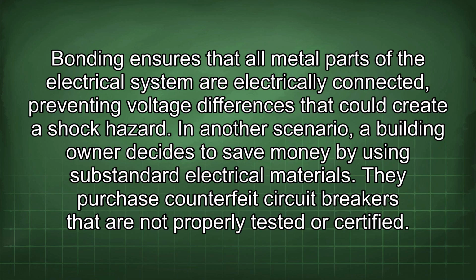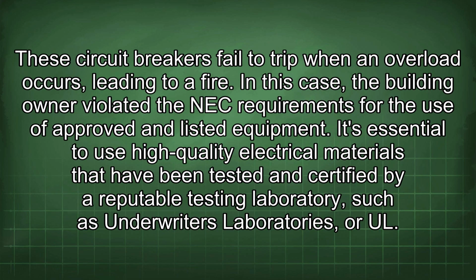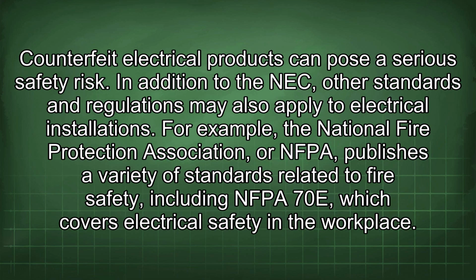Bonding ensures that all metal parts of the electrical system are electrically connected, preventing voltage differences that could create a shock hazard. In another scenario, a building owner decides to save money by using substandard electrical materials. They purchase counterfeit circuit breakers that are not properly tested or certified. These circuit breakers fail to trip when an overload occurs, leading to a fire. In this case, the building owner violated the NEC requirements for the use of approved and listed equipment. It's essential to use high-quality electrical materials that have been tested and certified by reputable testing laboratories such as Underwriters Laboratories. Counterfeit electrical products can pose a serious safety risk.